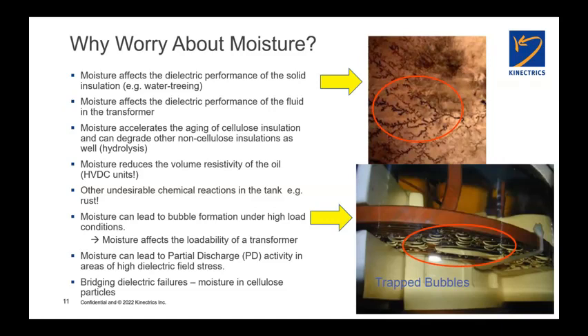And on the right top of the slide there, you see some classical water treeing that's taking place on the surface of the paper. And that's a partial discharge related activity caused by excessive moisture in the bulk of the paper. Similarly, moisture can affect the dielectric performance of the fluid. And by the way, in most of this presentation, I'm really going to be talking about mineral oil.